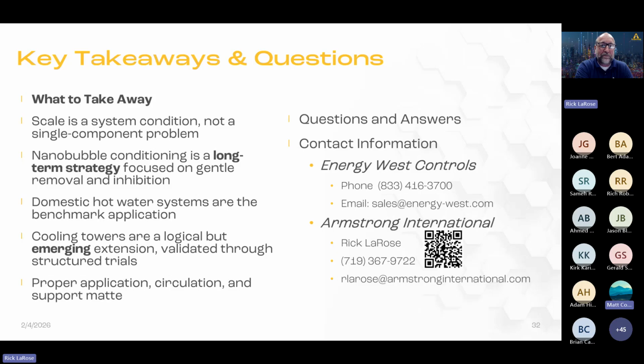Could you use a conductivity measurement upstream and downstream to continuously monitor performance, assuming that as scale is removed, conductivity would increase downstream of the nanobubbler? We have not done that. What we do during startup and validation is water chemistry analysis, and the cause and effect we see is, for instance, the hardness of the water increases as legacy scale releases into the water, increases in calcium, increases in magnesium. So we've approached it more from evaluating water chemistry rather than continuous monitoring, but that's an interesting idea.